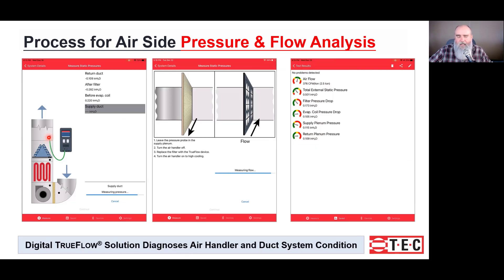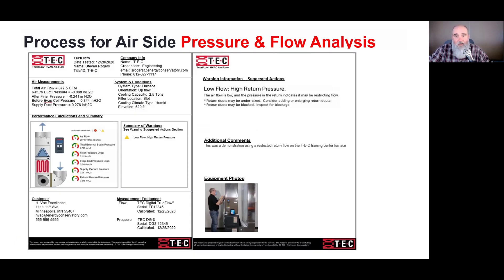So far we've only talked about taking a reading in the supply, but we can see some other information here. The supply measurement is shown, but it also shows several places where we could measure the pressure drop across the evaporator coil, or get external static pressure. All those different measurements are listed, and one thing I really like is that it gives us gauges in an easy-to-understand format — red, yellow, and green.